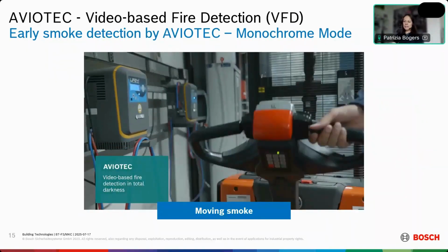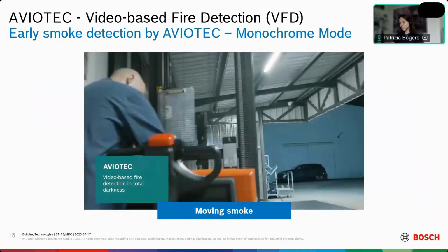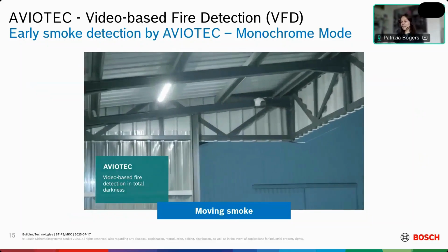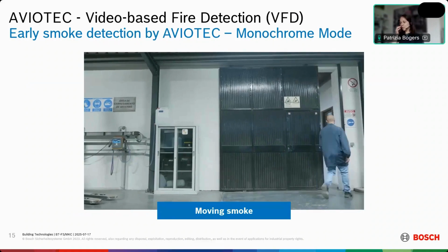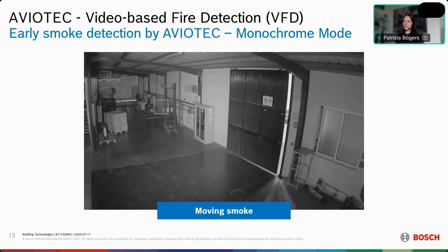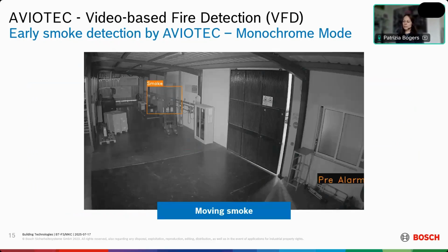Now let's have a look at night light, and without light, of course, detection. Here I brought a video that we took in our production in OVAR, simulating an event that can happen within those charging installations. The worker leaves in the evening and charges this vehicle, and now the fire incident happens. You see the smoldering smoke appearing.